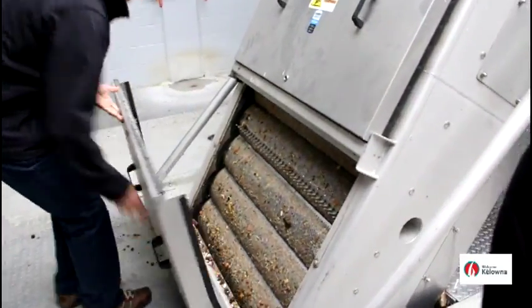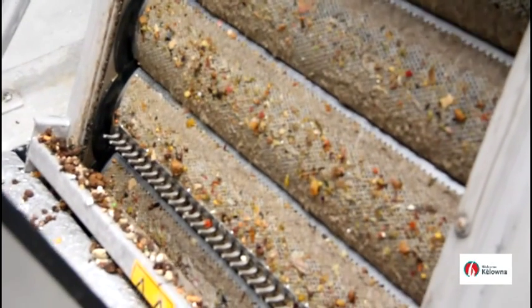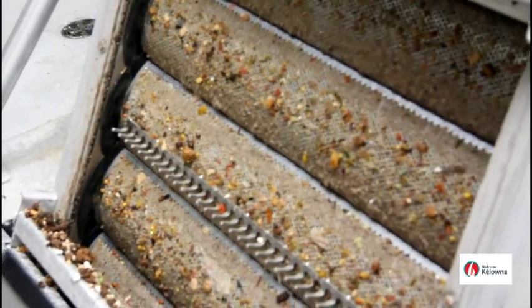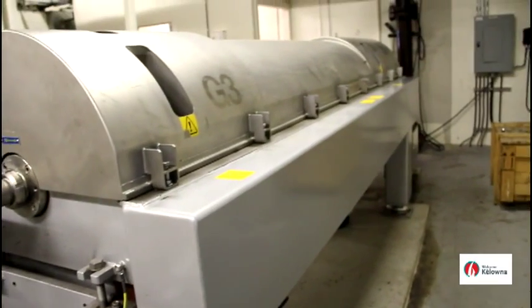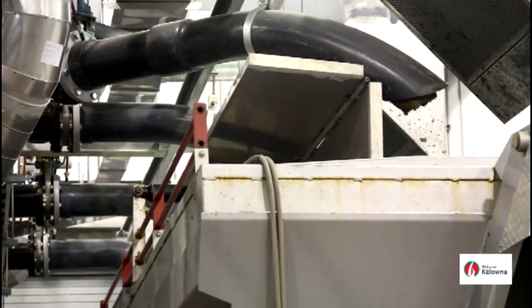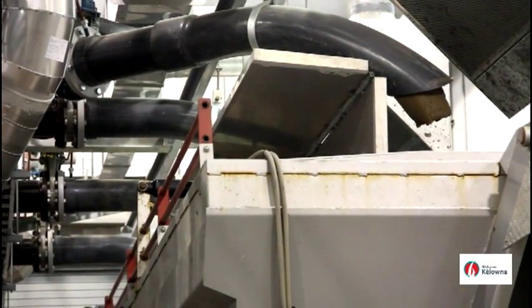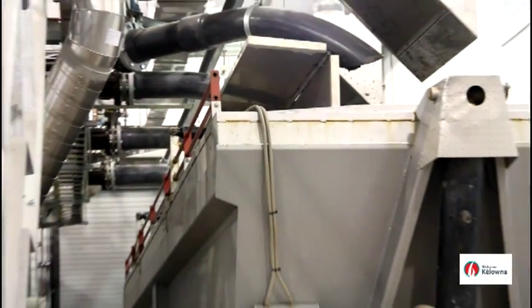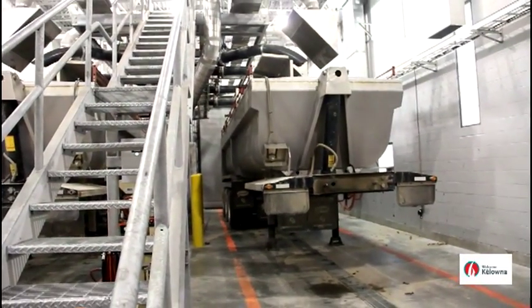There are three stages of the wastewater treatment plant: primary, secondary, and tertiary. In primary treatment, all the solids and screenings — sands, grits — nothing larger than six centimeters in diameter makes it past that area. Those screenings and solids are all accumulated and run through a centrifuge, which spins out the water creating a thick condensed sludge. That sludge is then pumped into large end-dump trailers, which are taken off site to a facility where they are land-applied to gravel pits for reclamation, handled by a private contractor.